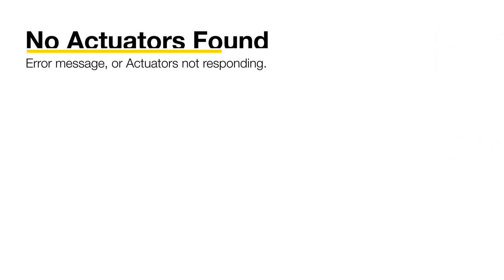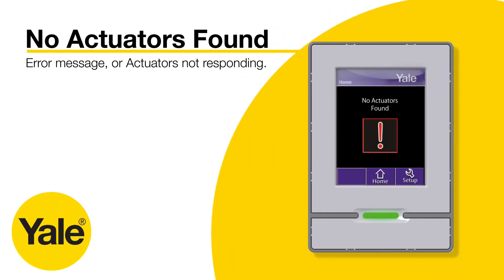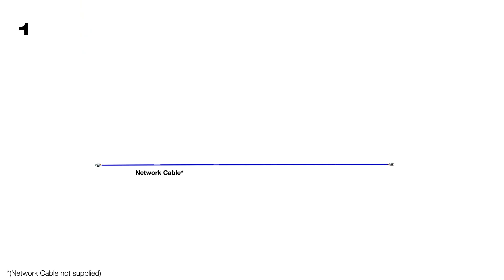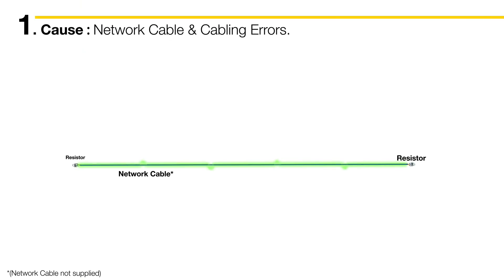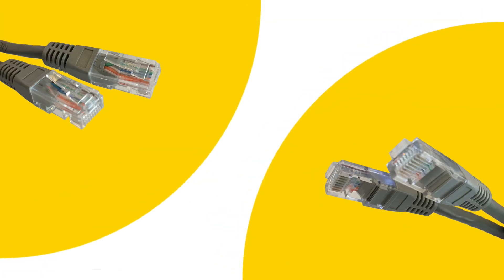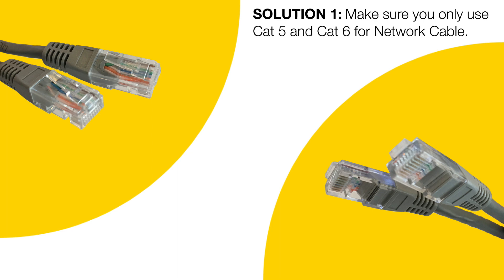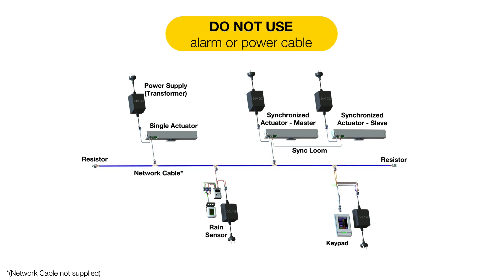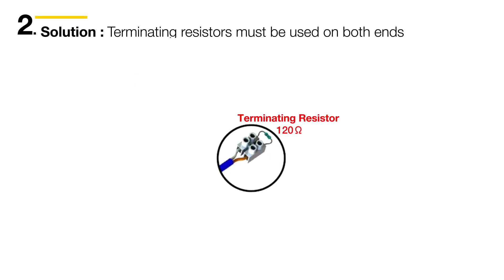If you're getting a No Actuators Found error message, or the actuators are failing to respond to an open command, one of the most common causes is the network cable. The network cable carries data communication signals between all the devices on the network, so you must use data cable with twisted pairs. Cat 5 or Cat 6 data cable works well. Cable that does not contain twisted pairs, such as alarm or power cable, will not work, as the network needs a cable impedance of 120 ohms to communicate properly.